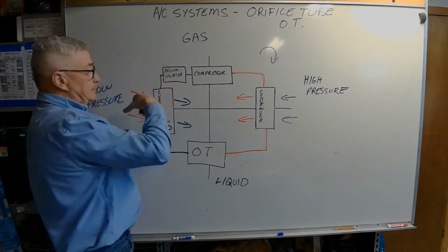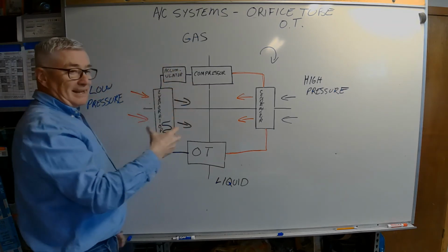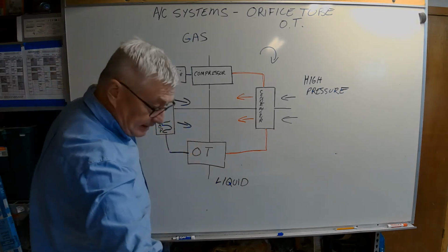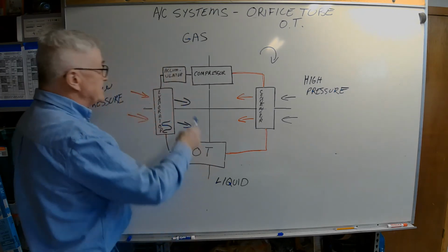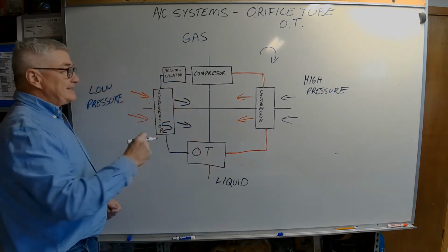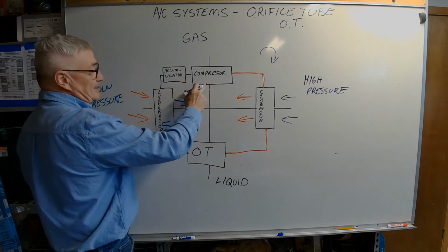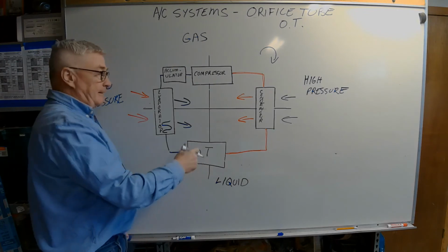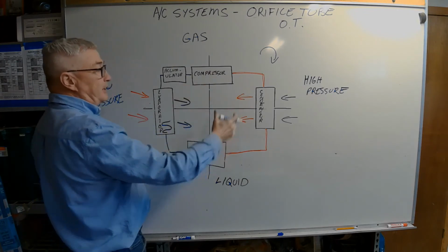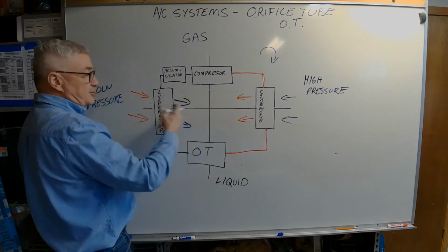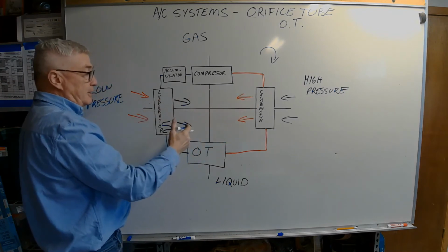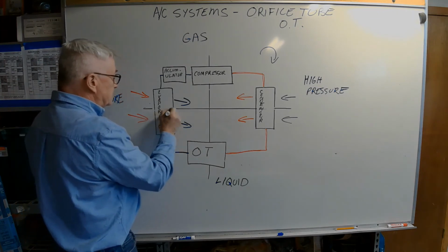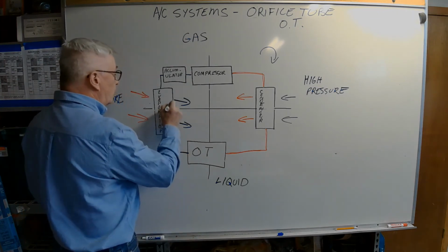And it acts again as a little bit of a storage reservoir. One of the reasons why we have the accumulator here is as a safety device in essence for the compressor. Because the orifice here is fixed, if my compressor continues to run and we don't have the right amount of heat exchange over my two heat exchangers, then I may end up with a case where some liquid may work through and into here.